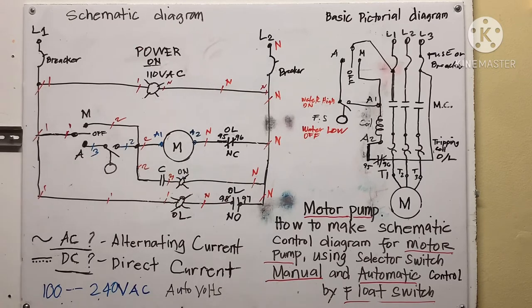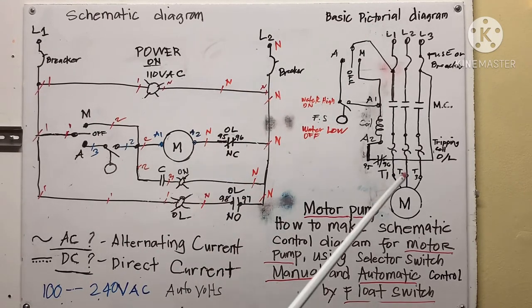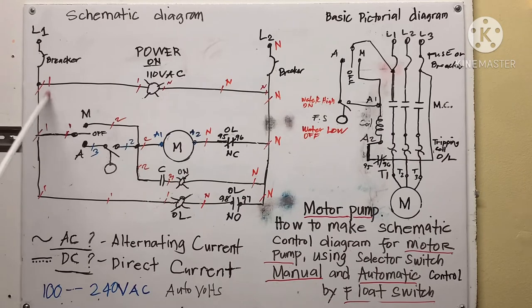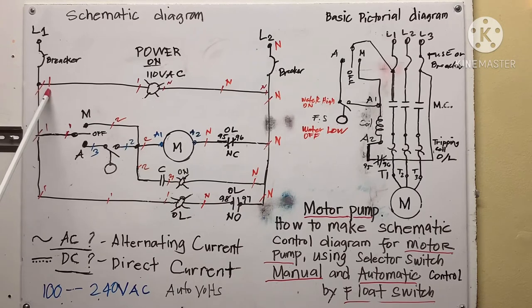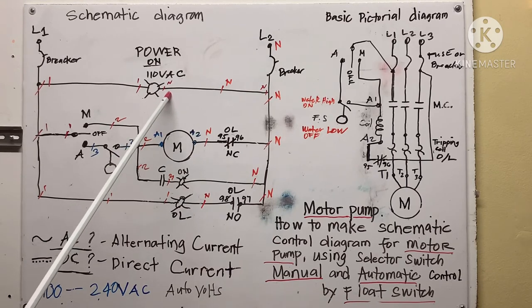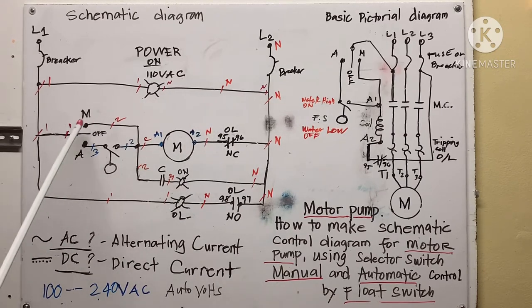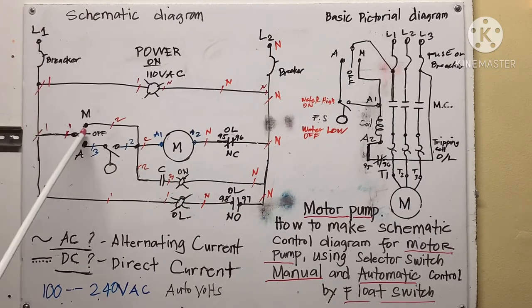As I mentioned in my first tutorial, we're going to make wire numbering — that's important so it's easy to troubleshoot. You put the number end to end: number one goes to the power for the power-on indicating light, through the selector switch, and neutral is number one all the way through.